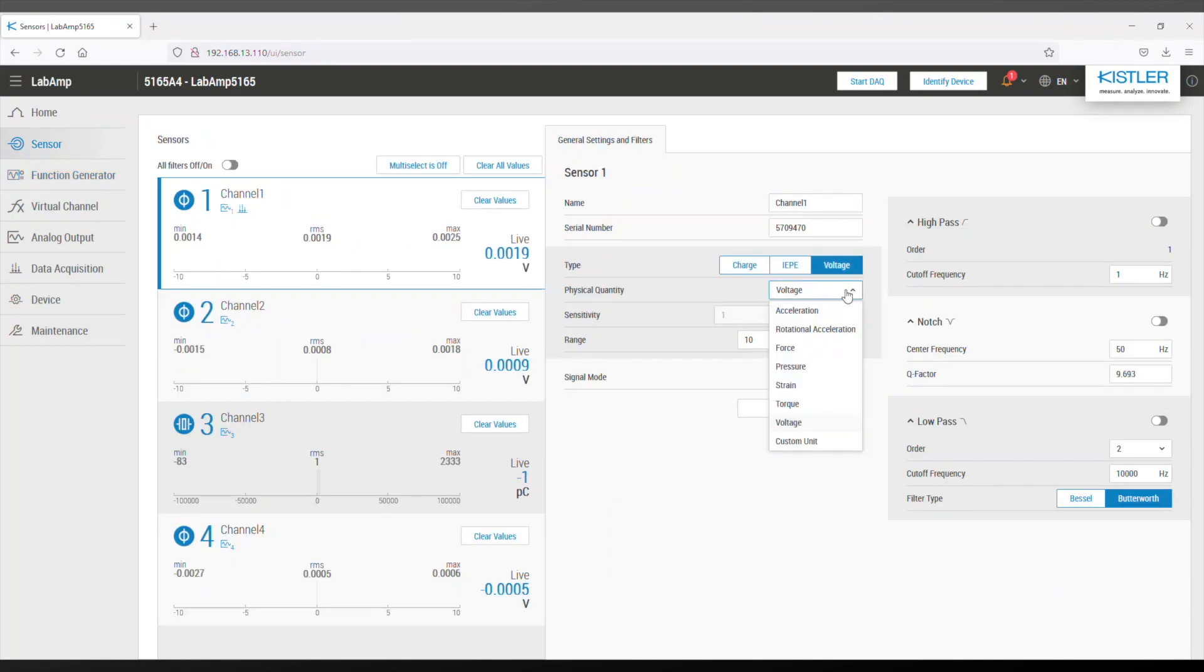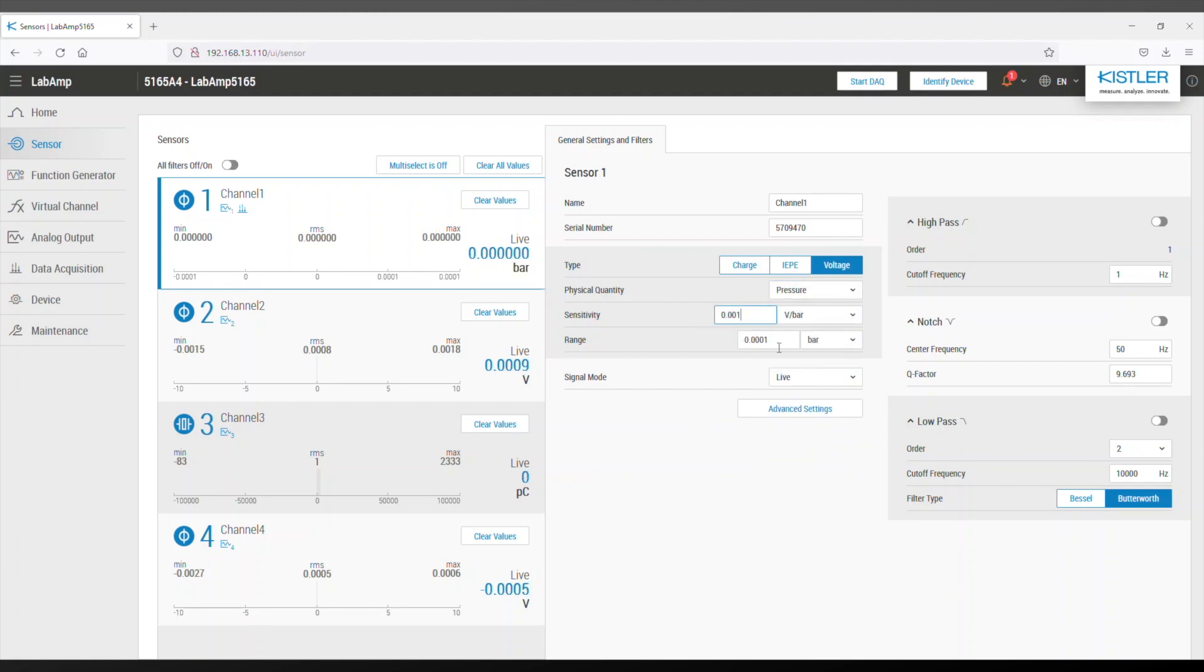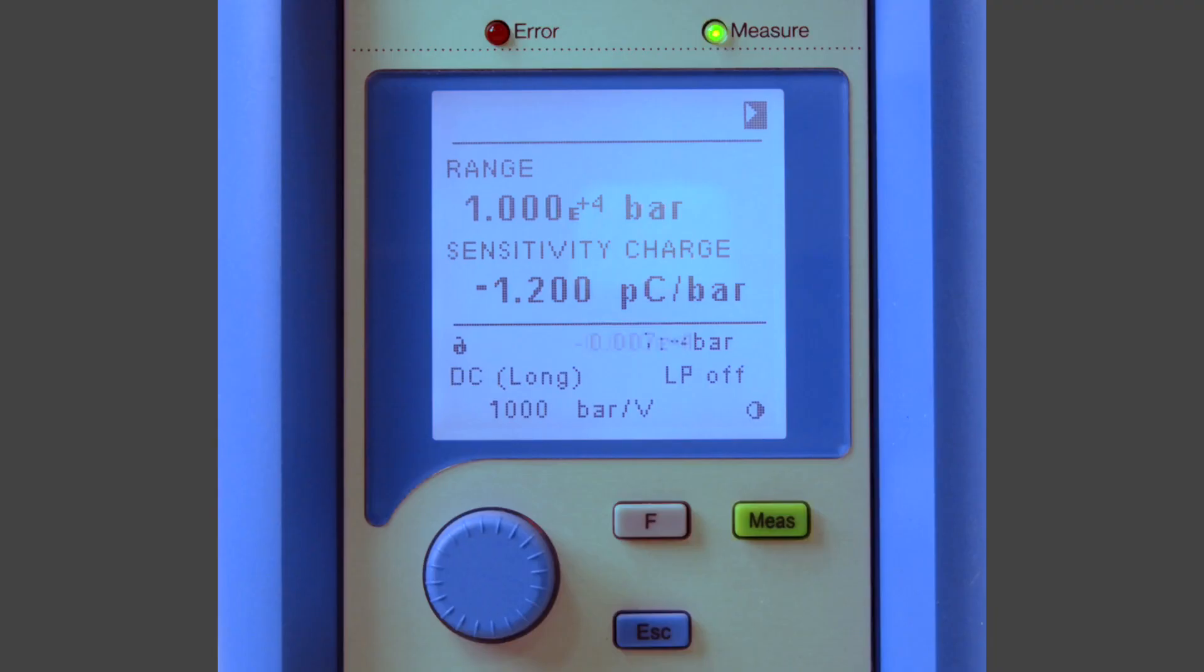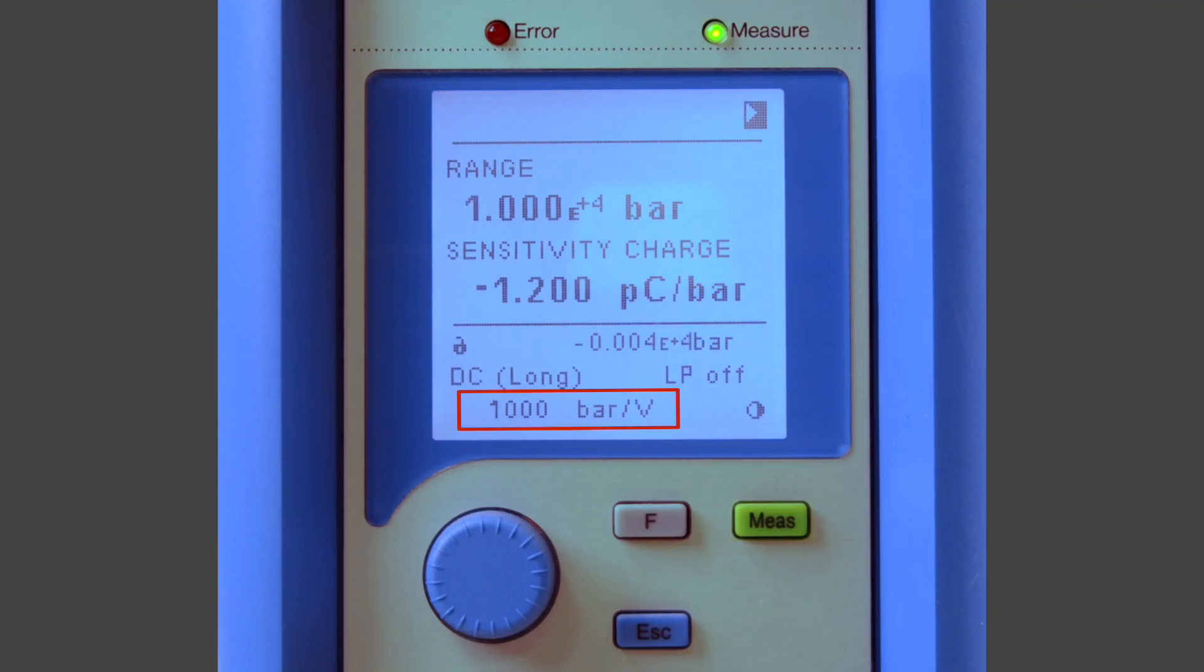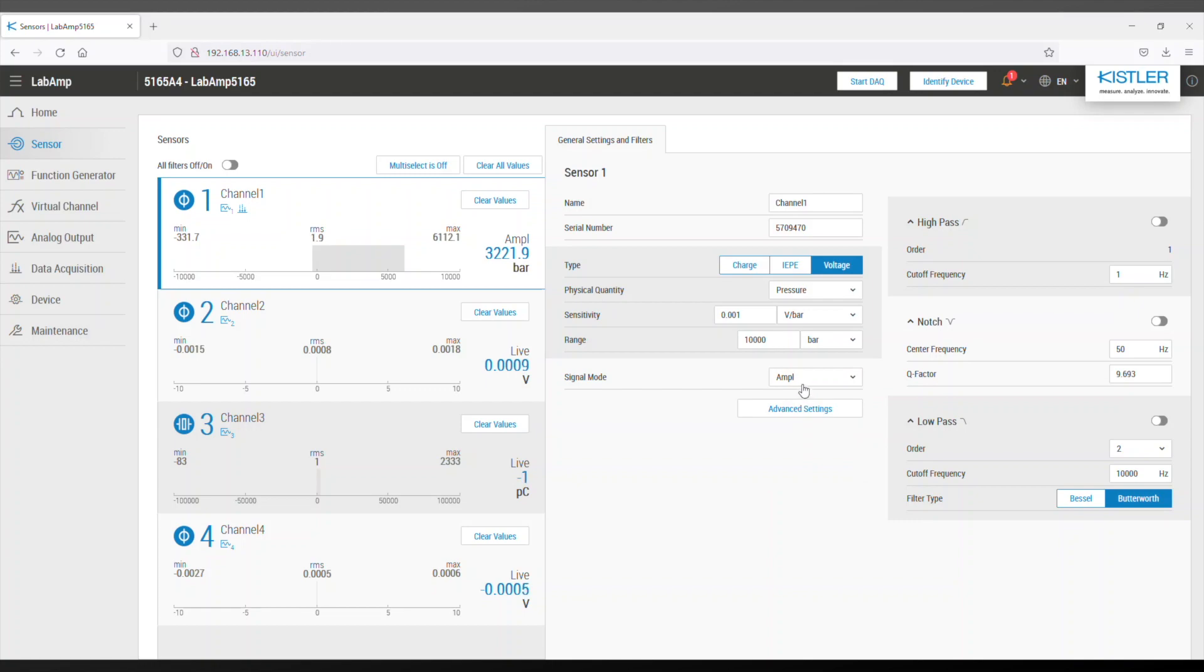Next, we will need to configure the input of the lab amp. I have set up my 5018 to a range of 10,000 bar to make sure I don't accidentally clip my signal. As you can see on the display, we expect 1000 bar per volt. I select amplitude to read it directly from the UI.